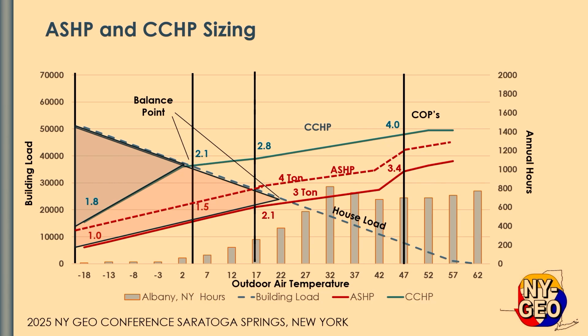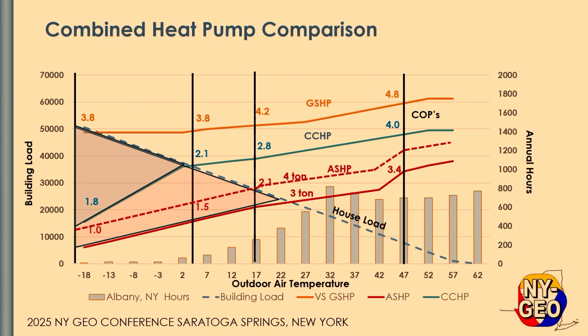So it is something that's going to have to be dealt with, even though there's not a lot of hours there. From a utility perspective, they don't really care how many hours. All that's got to happen is once, and that hits their peaks. So now we're going to add the combined. I've got the ground source heat pump added in here, and this is the orange line for that variable speed ground source heat pump.